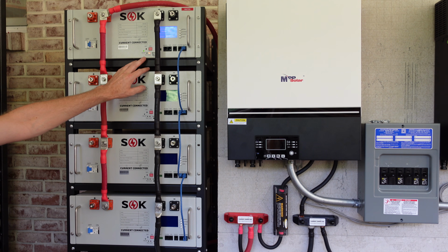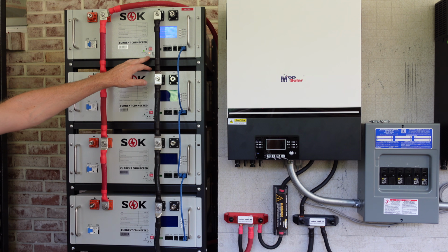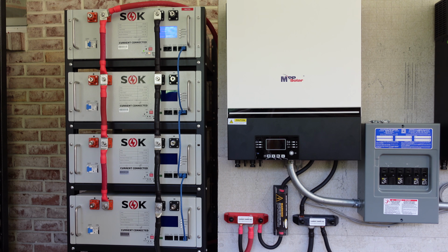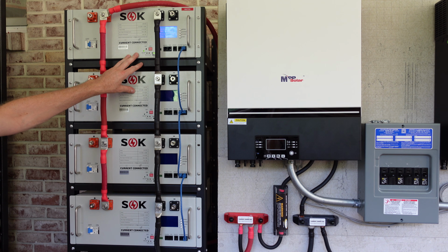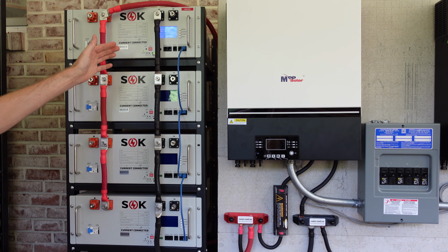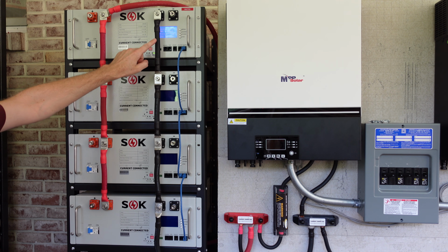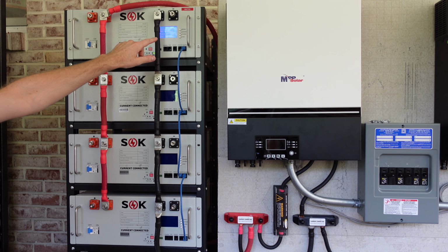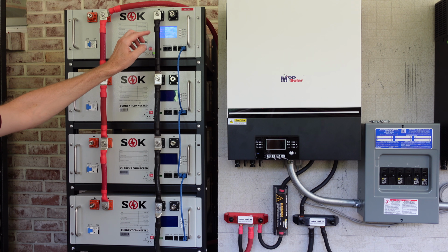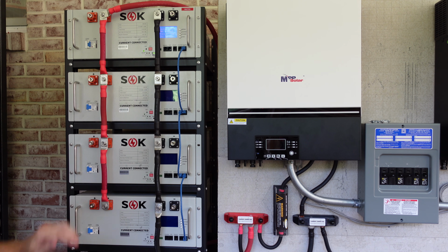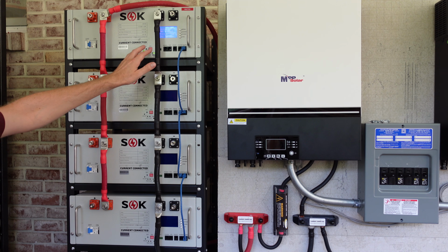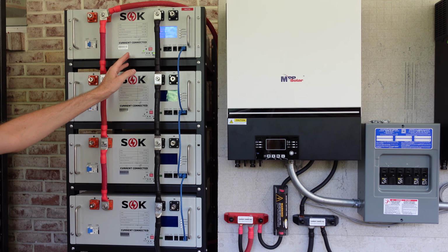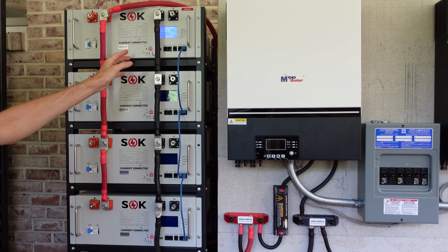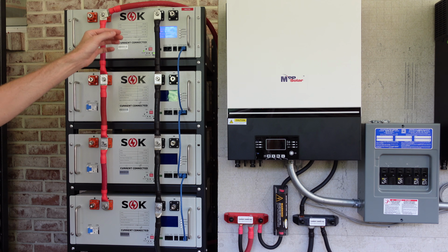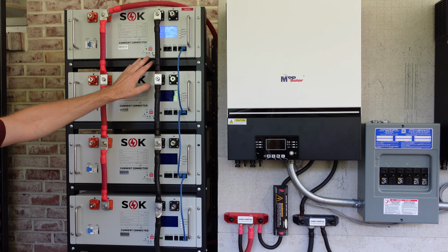And I see this is actually in the alarm state here, so perhaps we overloaded it somehow. I'm going to take a look at that. Alright, so that actually does appear. I guess that's how the pre-charge works. I don't know. It went into the alarm state, and I went in the analog info there, and it said SCP, or short circuit protection. I was going to grab the camera and get a clip of that. It clicked once more. It said 2 amps, and then it went back to SCP, and then it clicked a third time, and now it's in the run state.